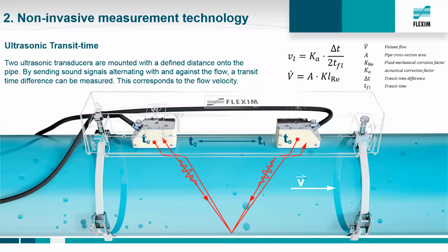The flow measurement system is a refractive system. This means that the ultrasonic signal is traveling through at least three different phases: the transducer wedge, the pipe, and the fluid. Each of these materials has different characteristics. When I talk about characteristics here, I mean specifically the sound speed. It is refracted at a certain angle at each phase transition. Multiplied by the acoustical calibration factor K alpha, this brings the sound speed of the medium in correlation with the angle of the ultrasonic beam into the calculation.